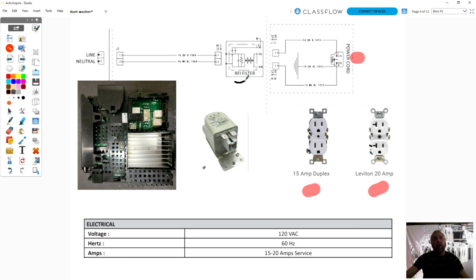Okay, so here we have the RFI filter. We call them line filters. We call them noise filters. These filters are there because the motor has an inverter on the board, and we're changing the voltage from AC to DC and controlling that motor with a frequency, changing the frequency of electricity coming in. If you look, our power supply coming in, hertz is our frequency, 60 hertz. When you look at your car radio and you listen to channel 100 or channel 96 on your FM radio, that is the frequency. So what the board does is it takes this 120 volts, 60 hertz coming in, and it raises the frequency, and it raises or lowers the voltage. It converts it from AC to DC.